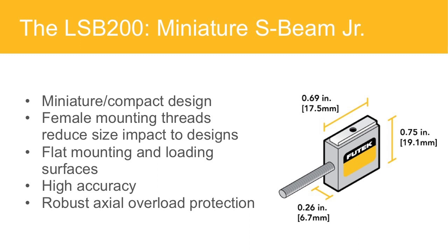Performance, 0.1% nonlinearity, small package size with tight centerline capability. The base design allows for tight centerline locations in applications such as keyboard testing, steering wheel switch testing, where positioning of multiple sensors becomes critical. The mechanical overload stop is also extremely important in automation applications where we have a potential for mechanical overload.